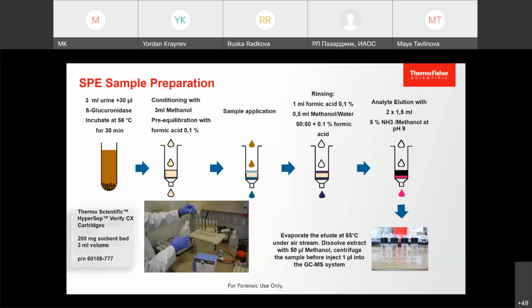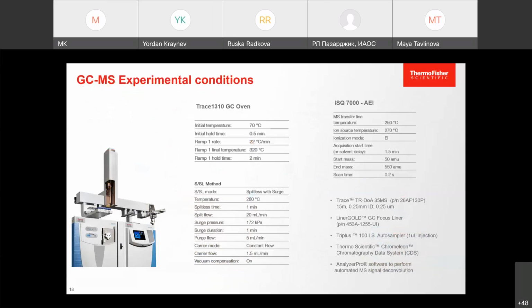1 microliter into the GCMS system. From experimental conditions, we are using ISQ 7000 with the advanced ion source. You can see the ion source temperature is 270 degrees. For the column, we are using a TraceGOLD column specifically for analysis of these compounds, and a special gold liner for this analysis. And of course, Chromeleon software for the data station.